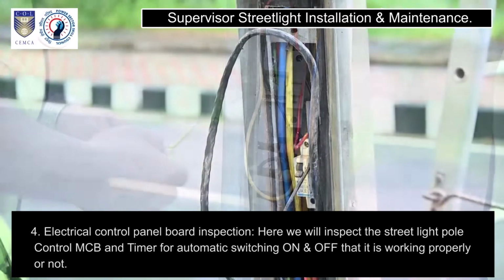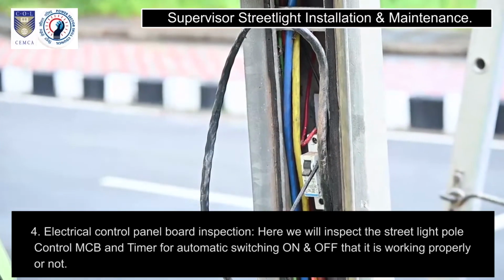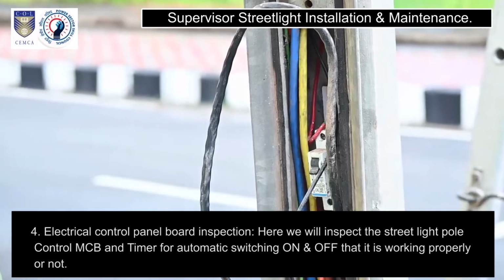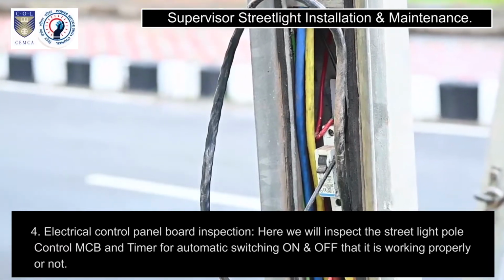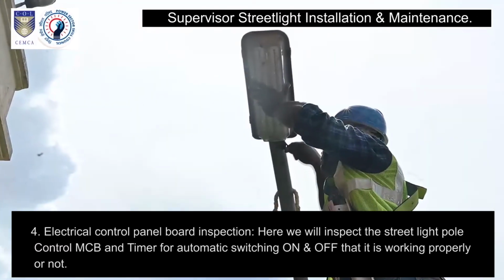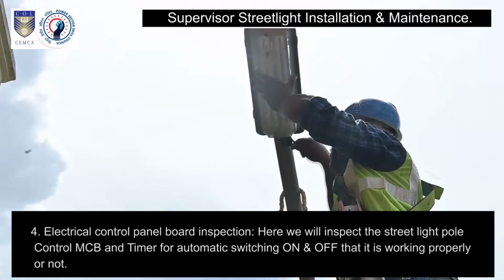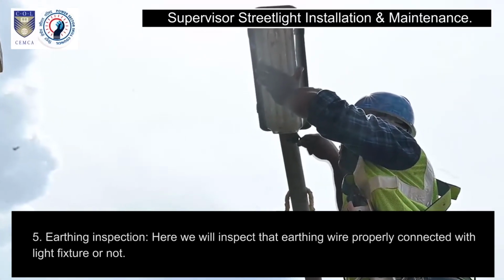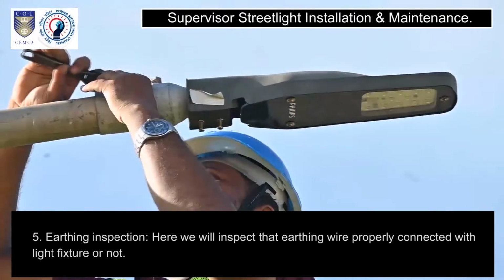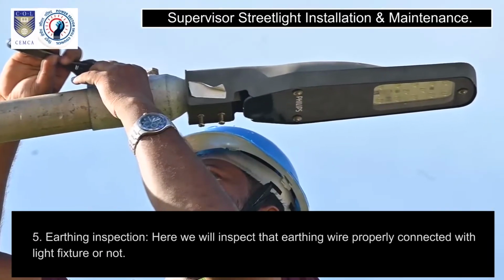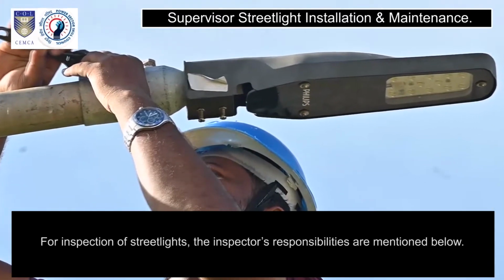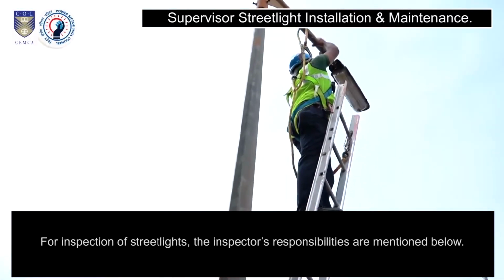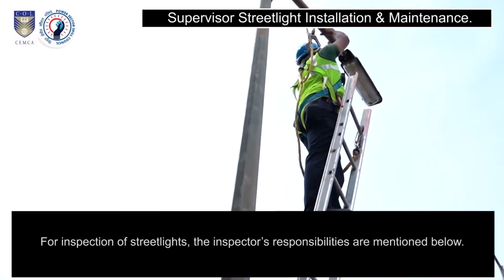4. Electrical control panel board inspection. Here we will inspect the streetlight pole control MCB and timer for automatic switching on and off, that it is working properly or not. 5. Earthing inspection. Here we will inspect whether the earthing wire is properly connected with the light fixture or not. For inspection of streetlights, the inspector's responsibilities are mentioned below.